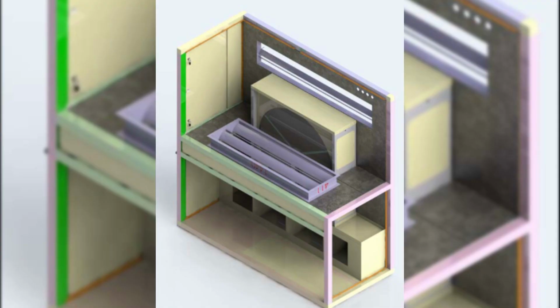5. Heating and cooling. SCA HVAC systems should provide ventilation air at 65 degrees Fahrenheit during heating, with terminal heating, such as electric or hot water convectors, in the PA spaces. Kitchens should have reheat electric or hot water coils. In cooling mode, units are coupled with a mixed variable air volume system. Capital improvement projects. 6. HVAC system. These projects must use commercial single-zone VAV rooftop heat pump units.